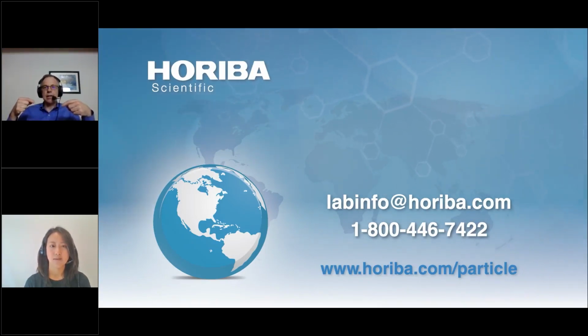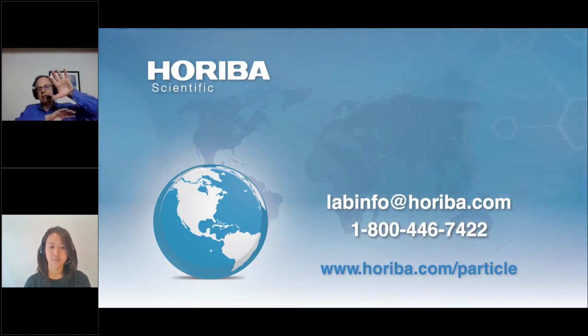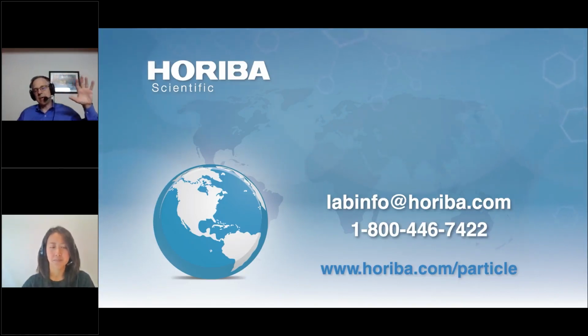Okay, so the math is getting two things. It's getting all the experimental data, and it's getting a couple numbers with the RI, and then it spits out a size distribution. Well, that input of the experimental data, the intensity on the detectors, if that's always the same, you always get the same answer out. And so if I have a repeatable method, my raw data coming in is always the same.